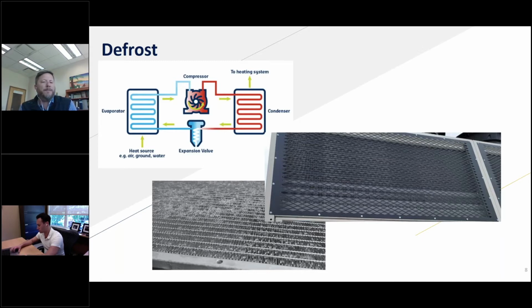So the evaporator temperature, the refrigerant temperature inside the evaporator, drops as the ambient temperature reduces. Once we get to and below freezing, as we approach 32 degrees and really as we get below 32 degrees, depending on the amount of humidity in the air, we have the potential to frost a coil or form ice on the coil, because moisture in the air is hitting that really cold surface, and we then start to make ice, okay?